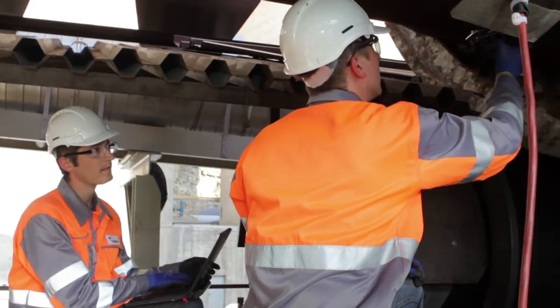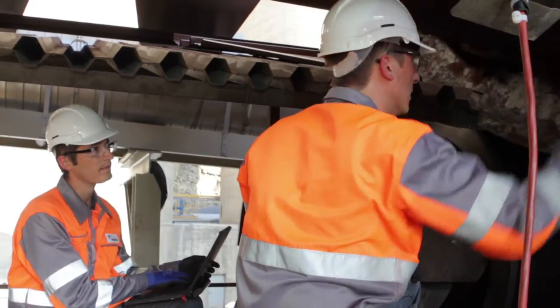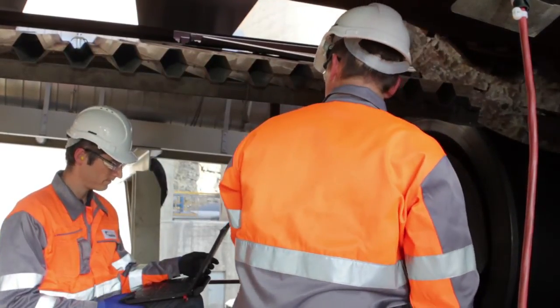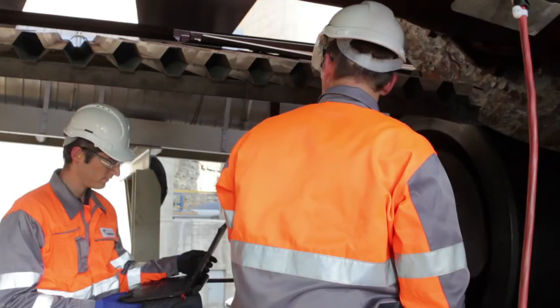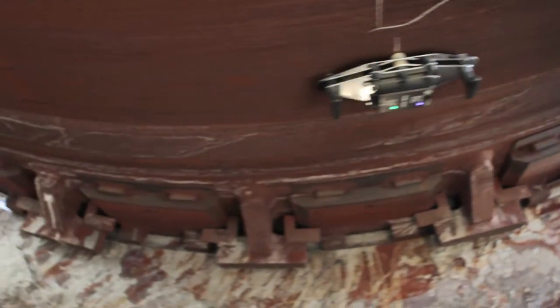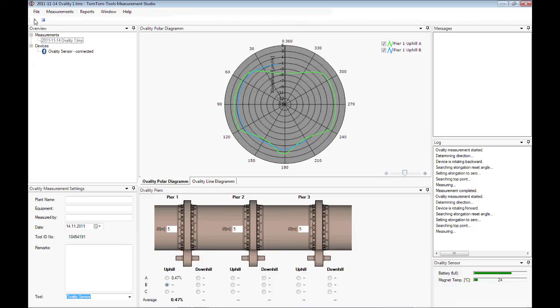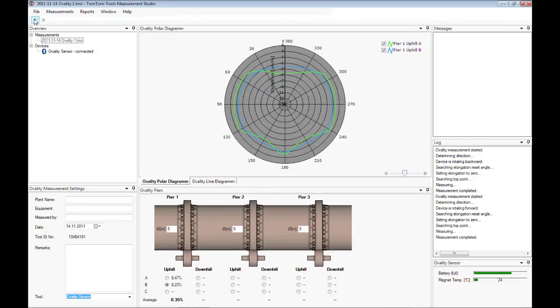Due to the fact that the ovality is most dominant under the tires, the measurement should be taken in close proximity to them. Distances of 1 to 1.5 meters between tire and tool are okay and normally give only negligible errors. The values of the relative ovality are directly calculated and displayed in the lower center window.